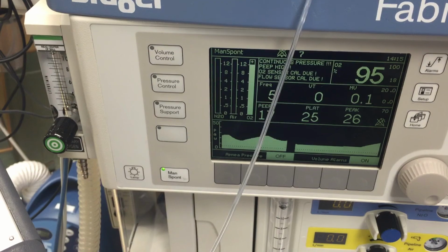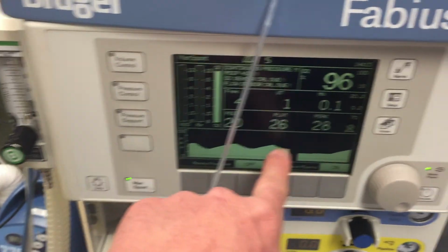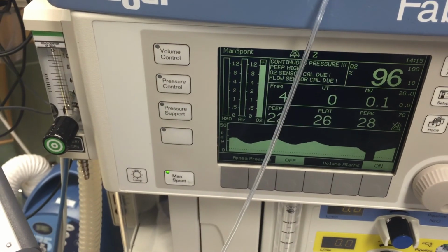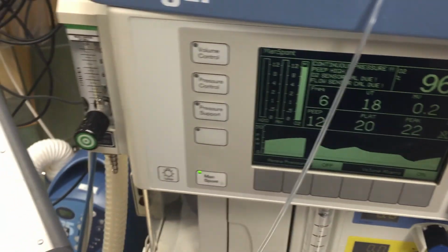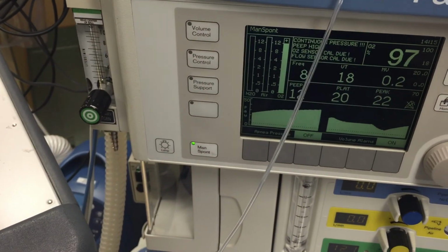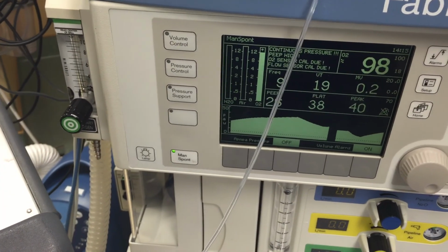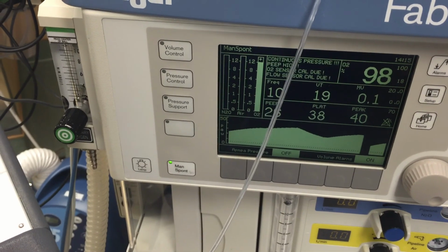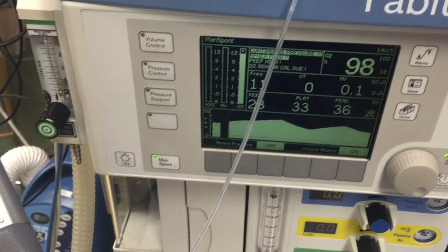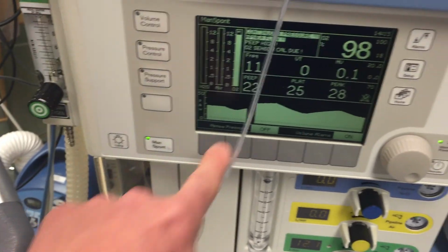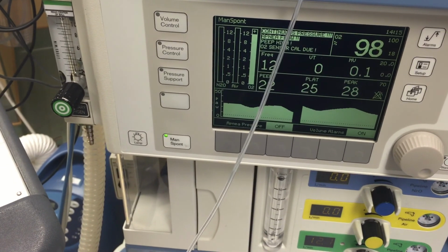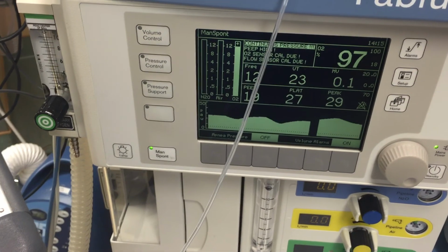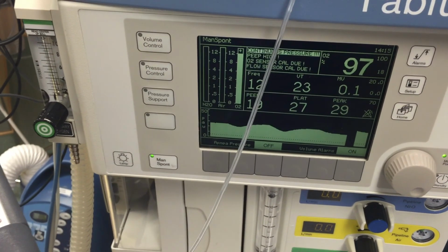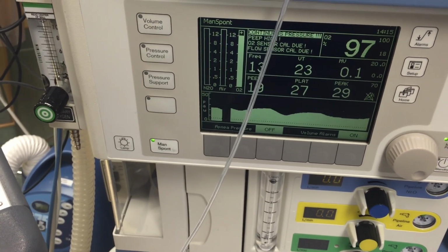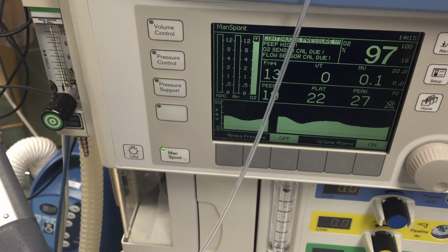The third parameter you want to look at is known as the pressure waveform curve, as shown here. Anytime the pressure waveform curve dips, like so, that means a negative pressure was generated. The only place a negative pressure can come from is the patient inhaling and sucking gas from the bag. When the pressure goes back up, that shows that the patient is exhaling. This is another way to prove to the clinician that the patient is maintaining effective ventilation and that a continuous positive airway pressure is being applied.